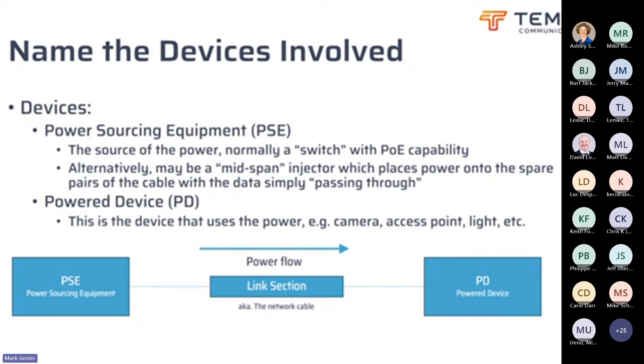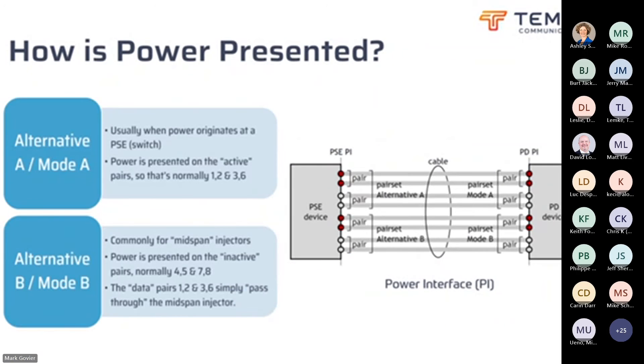Let's talk a bit more about the presentation of the power — this is where it gets complicated. The power interface, that's the connector at which the data and the power are being presented, is the sockets effectively at either end of the link. There are fundamentally two alternative ways of connecting the DC power onto the cables which are also carrying the AC signal. There's alternative A, which originates from the power sourcing equipment and is applied to the main signaling pairs — the primary pair set. This is the pair of wires that carries both data and power simultaneously. When it reaches the powered device, it's known as mode A. Alternative A and mode A are just two names for the same thing at opposite ends of the cable.